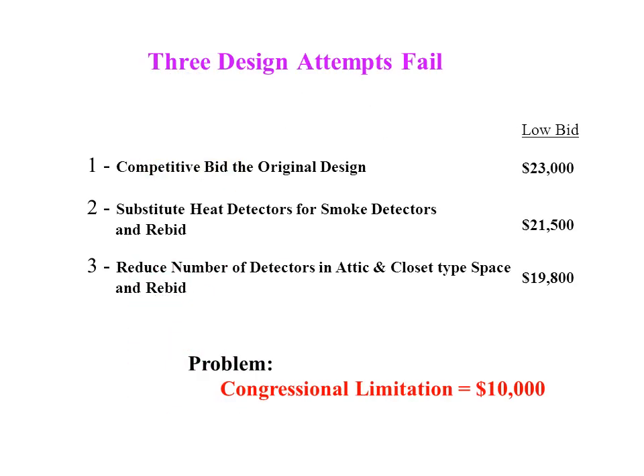When we received this project to value engineer, it was given to us as a mission impossible challenge. The boss didn't think we could do it because he had attempted to design it three times. The first bid came in at 130% over the budget set by Congress for residential improvements in any one year. The second design reduced quality to a minimal acceptable level by substituting cheaper heat detectors for many of the more desirable smoke detectors. The third design eliminated detectors in many spaces not considered primary occupancy — a stretch of the code, for surely the fire would not start in a closet.